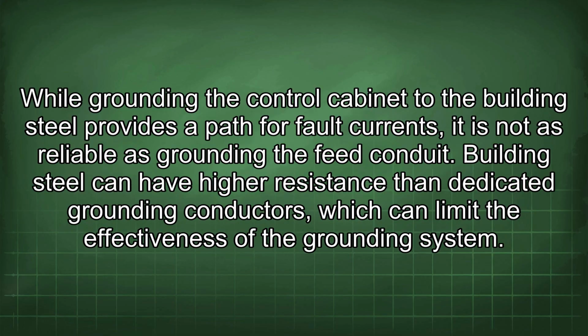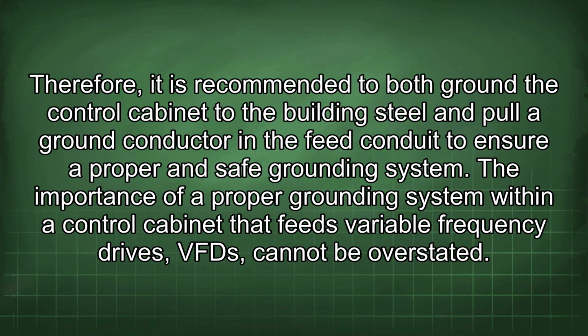faults. While grounding the control cabinet to the building steel provides a path for fault currents, it is not as reliable as grounding the feed conduit. Building steel can have higher resistance than dedicated grounding conductors, which can limit the effectiveness of the grounding system. Therefore, it is recommended to both ground the control cabinet to the building steel and pull the ground conductor in the feed conduit to ensure a proper and safe grounding system.